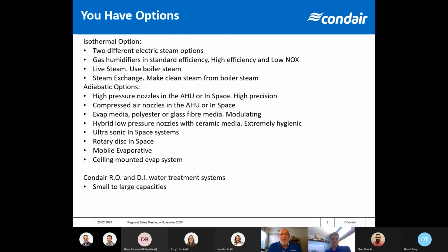Evaporative media, we have choices here too, with glass fiber or polyester media, modulating systems, and the hybrid system we talked about. We also have ultrasonics for in space. This is our lowest energy usage system that we offer. They're for smaller loads, up to 40 pounds per hour, but extremely low energy costs with those. We have a few others: a rotary disc, mobile evaporative systems, and our newest system we just came out with, our new ceiling mounted evap system. These fit up into the T-bars and ceilings. They're totally self-contained.